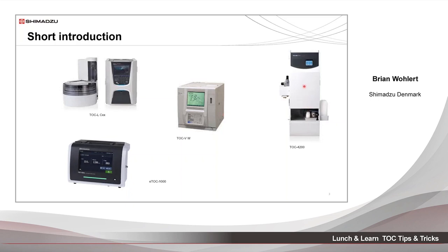The TOC-4200 was introduced back in 2012 and is an online TOC analyzer, which is more or less the same as the TOC-L, but this can be installed in, for instance, wastewater treatment plants. So we are able to have several streams into the analyzer.